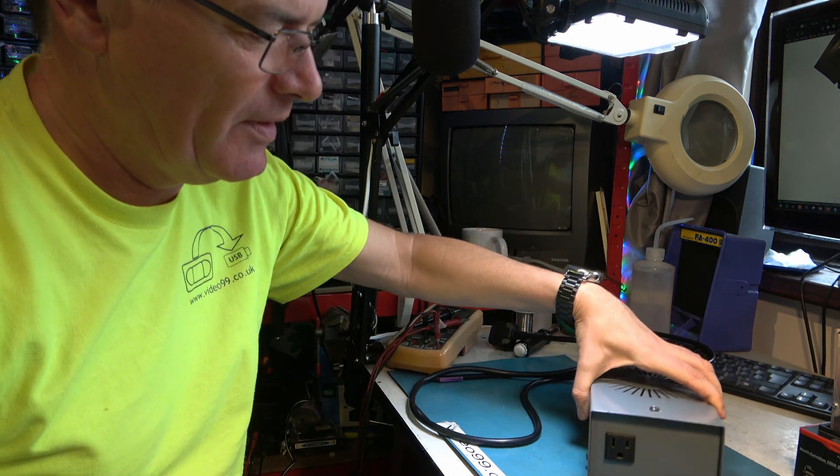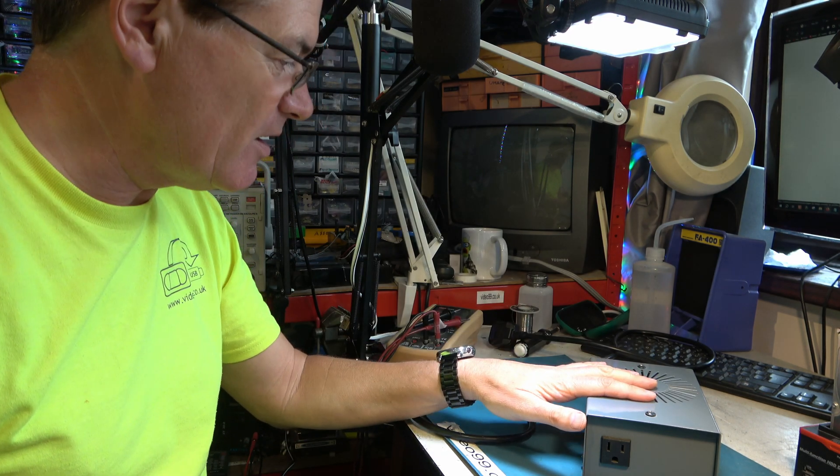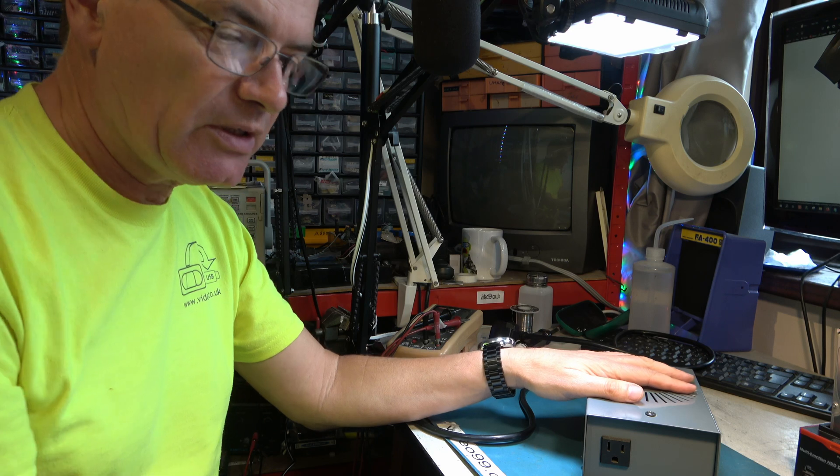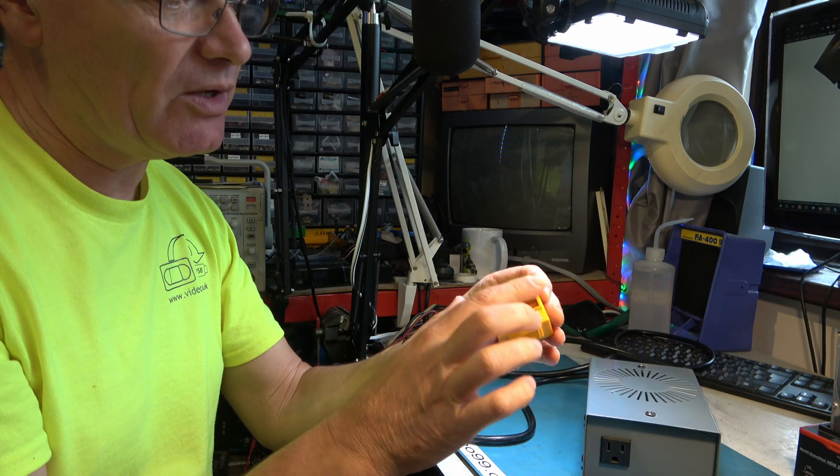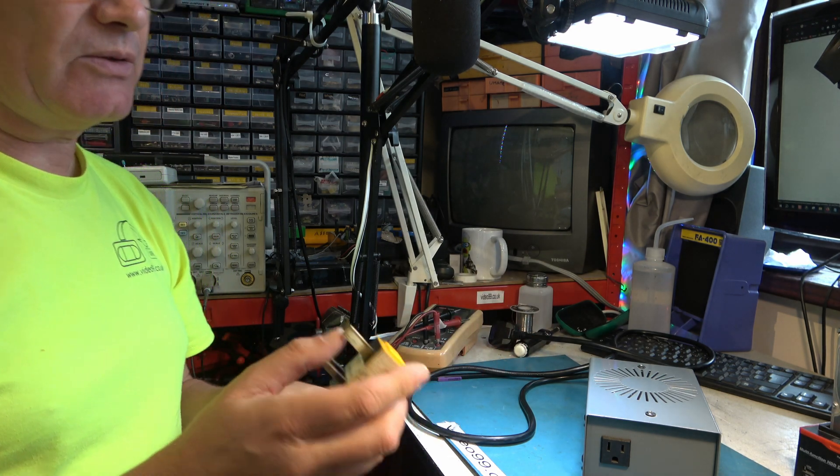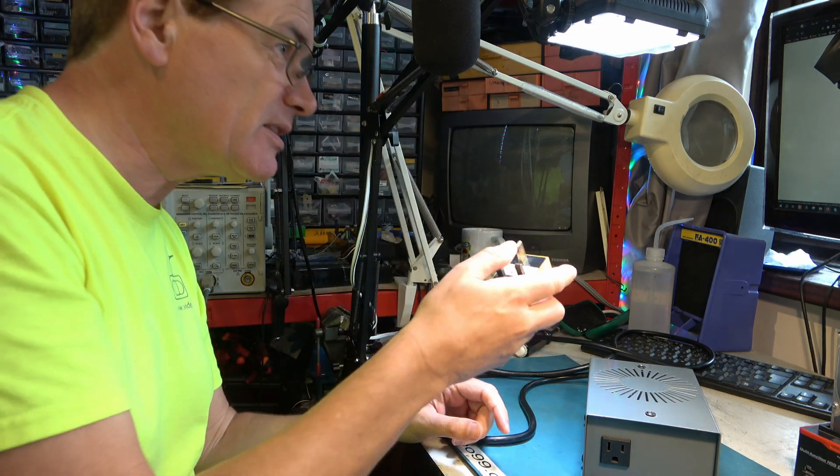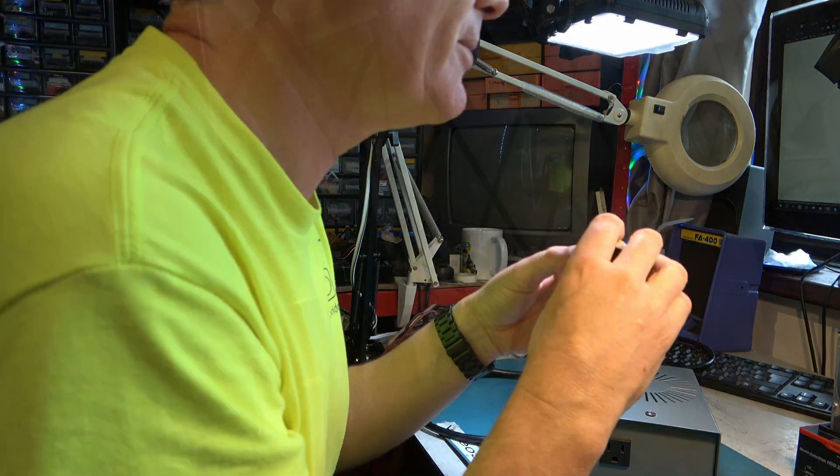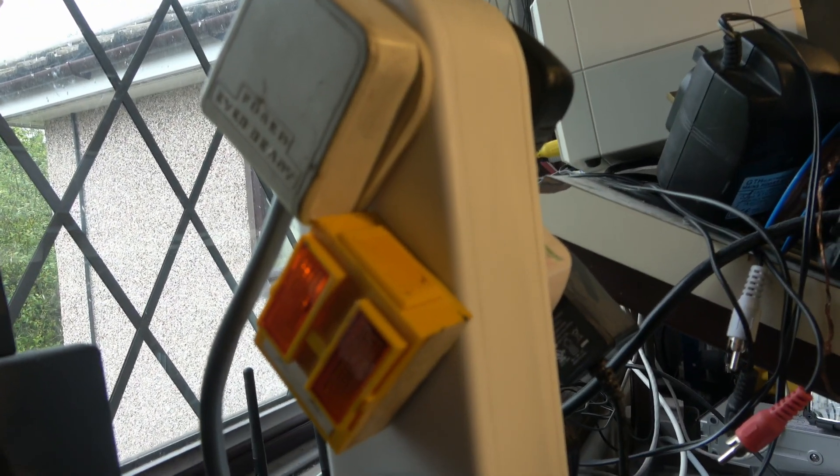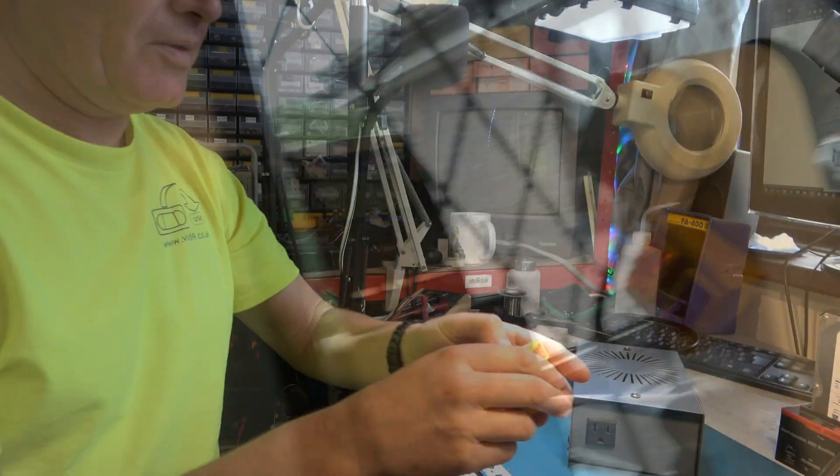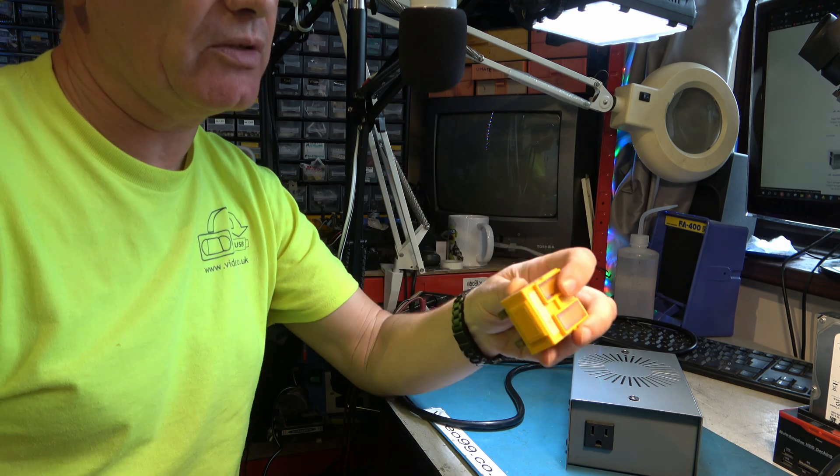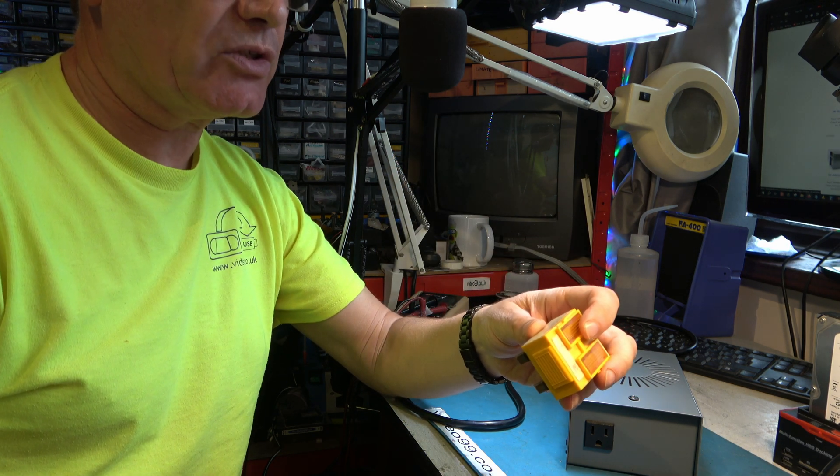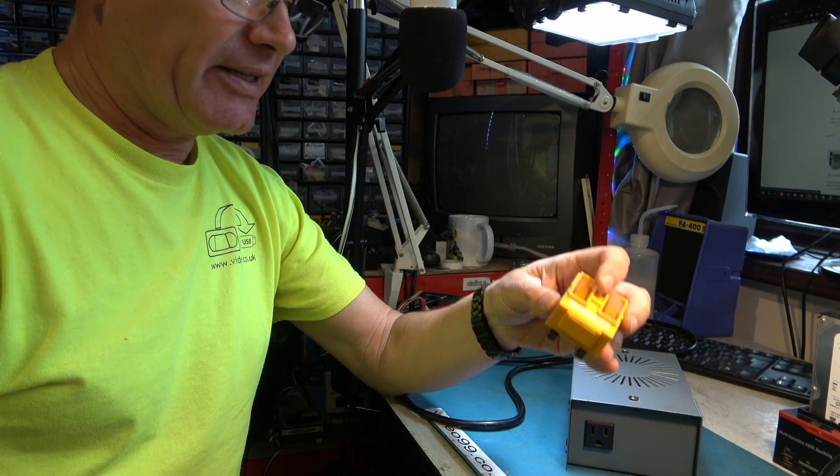What other mechanism could there be? Well, maybe this wasn't being held at earth. Maybe there's an electrical fault. So I have one of these cheap testers, but it's just got two neons, and it will tell you, if they don't both light up, there's a fault. So let's plug this into my mains distribution unit that I was using to connect this up and confirm that both lights come on. Oh, that's not right, is it? We have a fault. My notes here say that if just that light comes on, then either live and neutral are swapped or earth is disconnected. Oh, dear.